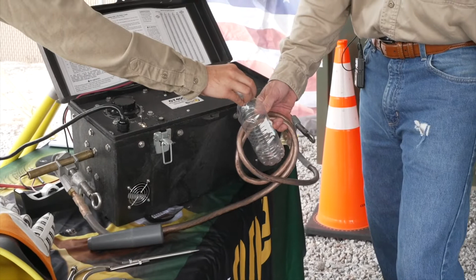Okay, Abby, now we're going to take the same current, and we're going to test. When you test your grounds, you're going to test them in a parallel configuration, maybe a 2x12 with 2x4s on each side, all right, or twisted. That's going to mimic that point A to point B parallel, and it mitigates most, not all, but most of that magnetic field, all right?